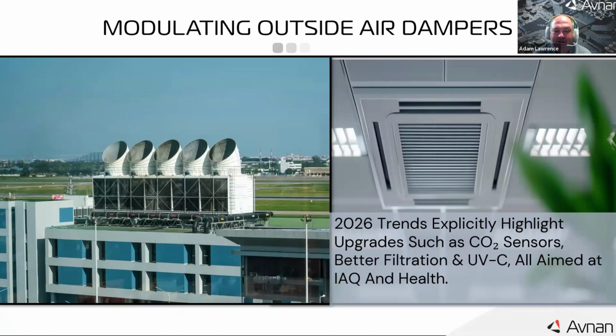Many modern systems are doing exactly this, modulating outside air dampers based on CO2 readings to hit the target indoor air quality. The benefit to the building owner is twofold: better occupant comfort and energy savings. You're not over-ventilating empty spaces, wasting energy, and you're not under-ventilating a packed conference room, avoiding drowsy occupants and high CO2 complaints. 2026 trends explicitly highlight upgrades such as CO2 sensors, better filtration, and UVC, all aimed at indoor air quality and health. A diagnostics-driven airflow control that can integrate those sensors is exactly what meets that demand.